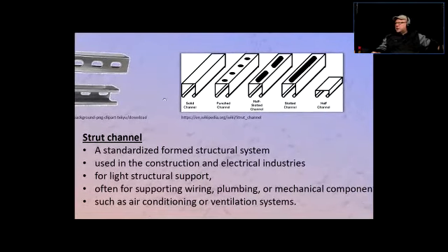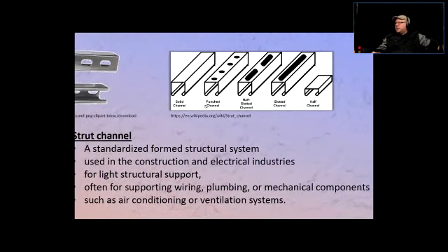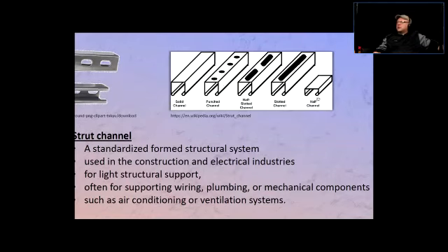You can buy longer sections of strut and cut them into pieces to use like Lego blocks. Common types of struts include solid channel, punched channel — which has openings or holes you can run screws or bolts through — half-slotted channel, which has slots in the U-shape, slotted channel, and half channel, which is basically not as tall.